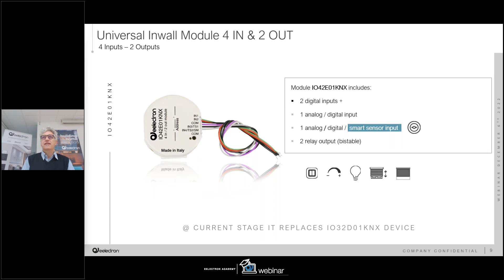We have two pure digital inputs, meaning we can connect them to conventional switches or conventional sensors. The third one is an analog or digital input, configurable by ETS as an analog input. When we say analog, we can connect an NTC probe to detect temperature. This third input can also be an interface to our smart sensor devices, which we'll discuss in a later slide.